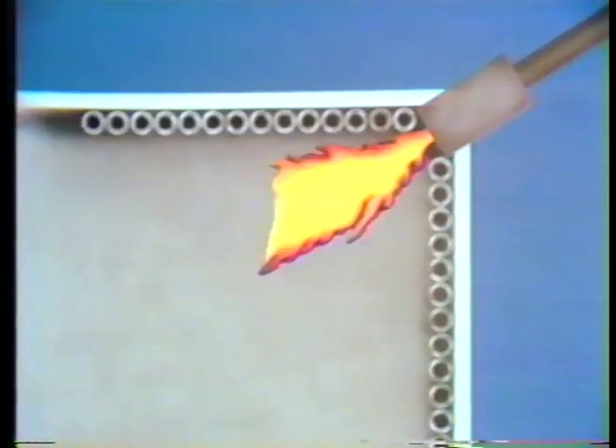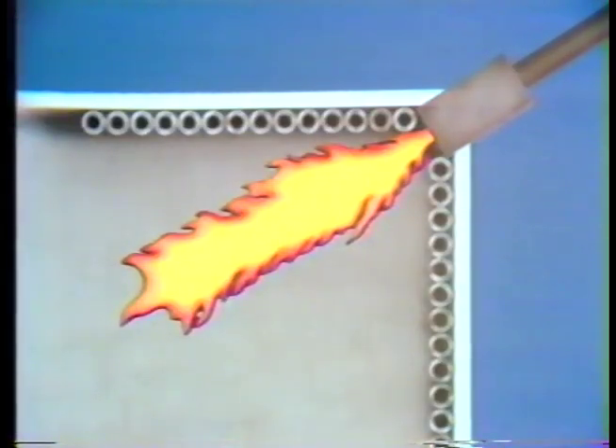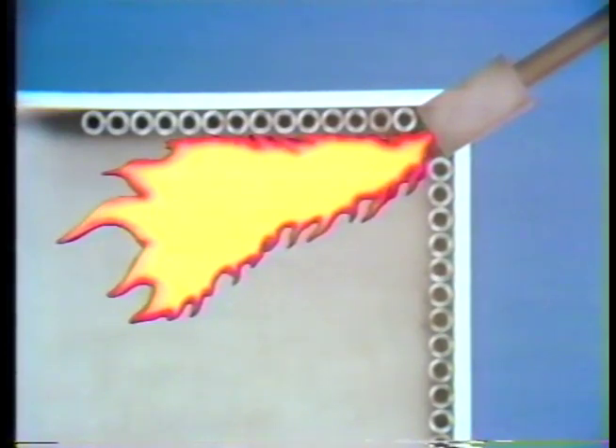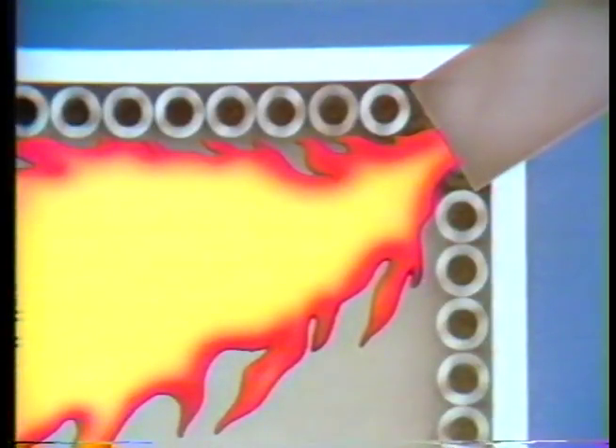The metal will overheat, weaken, and then rupture. Blockage in a tube can cause inadequate flow of water or steam. If the flow is so restricted that the tube can't be kept cool, tube failure from overheating will eventually result. Overheating from improper flow of hot gases happens when the tubes are exposed to more heat than the normal cooling flow can handle. One example is flame impingement — direct contact of furnace flame with the tubes. When flame comes in contact with the tubes, it can raise their temperature so high that they fail.